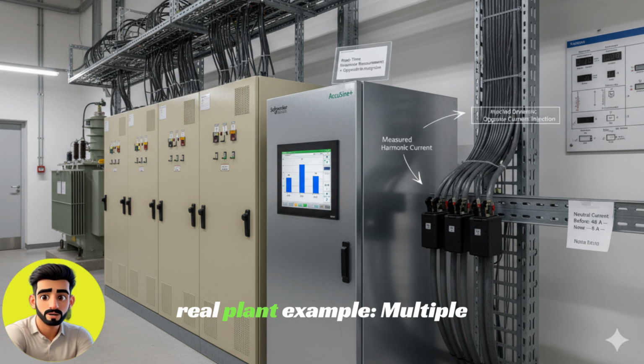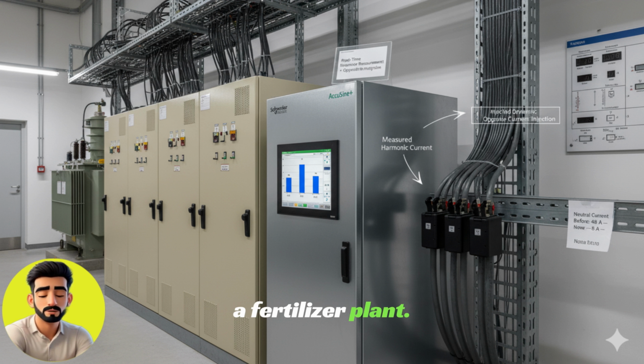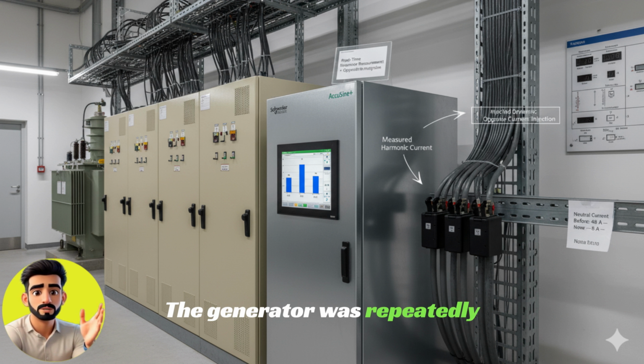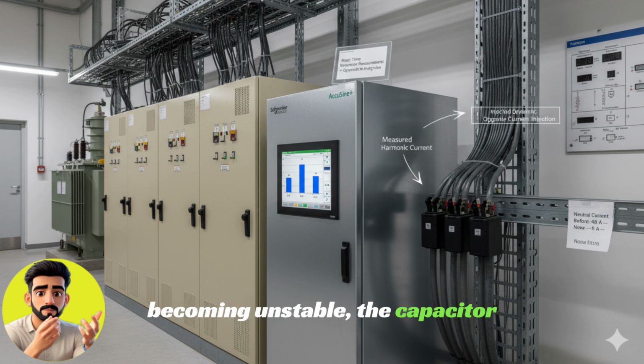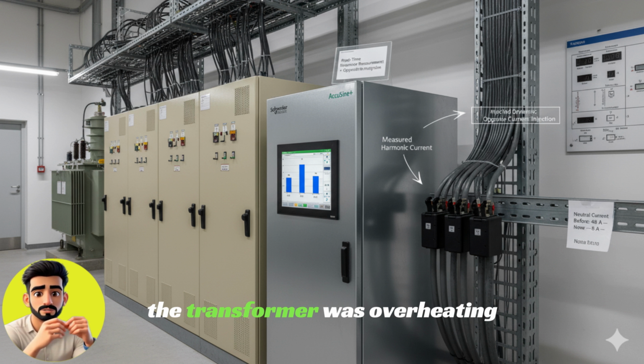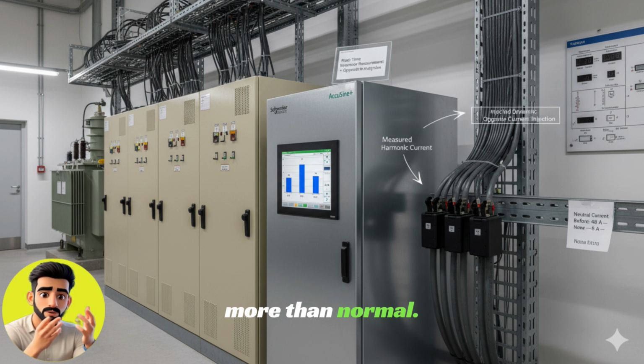Let's look at a real plant example. Multiple drives were installed in a fertilizer plant. The generator was repeatedly becoming unstable, the capacitor bank was failing, and the transformer was overheating more than normal.